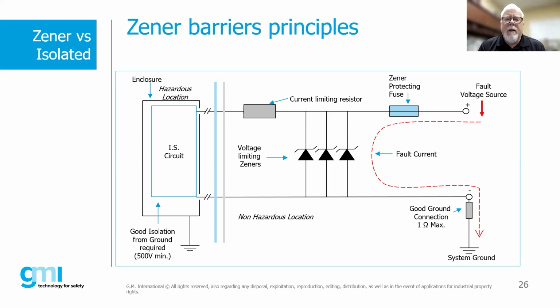Because of what Zener diodes do as the voltage increases, if you're not familiar with them, think of it in terms of a dam on a river. As the water gets too high, the dam starts to overflow and allows the water to spill over. So a Zener diode, as the voltage increases above its rating, if it's 28 volts and all of a sudden we apply 29, 30, 32, those Zener diodes will start to open up. They will allow that excess energy to go to ground, and then the Zener protecting fuse will actually blow, and in the hazardous area, we will basically have a dead device.